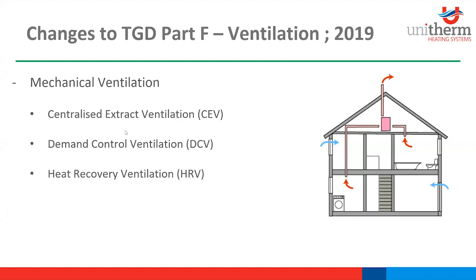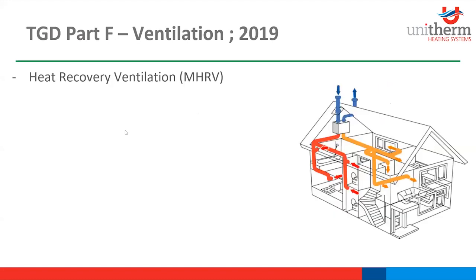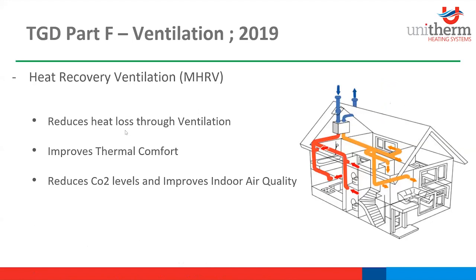So heat recovery ventilation is our most popular one, and it's basically the most efficient and best practice really for ventilation. So your heat recovery ventilation is extracting warm air from your wet rooms while heating the fresh air from the outside to your supply rooms. So just to go into that a bit further. With ventilation losses being the biggest contributor to fabric heat loss, by making our dwelling airtight and using HRV, we get a significant improvement on energy performance. The extract and supply ducts feed into a heat exchanger without cross-contamination to transfer heat from the warm air to the cold air at an efficiency of about 90%.